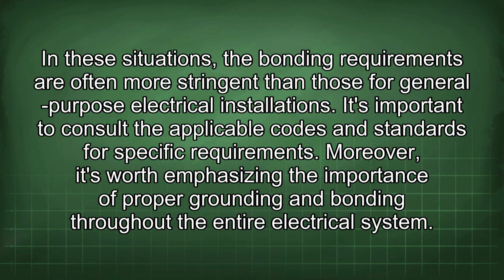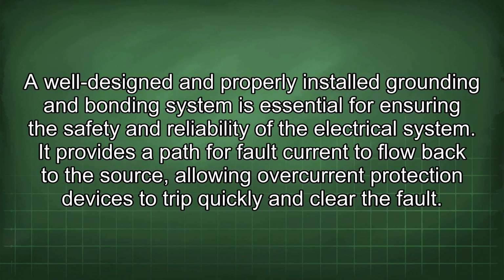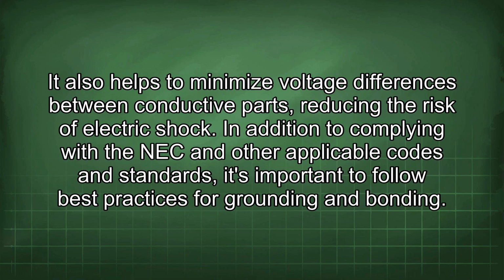Moreover, it's worth emphasizing the importance of proper grounding and bonding throughout the entire electrical system. A well-designed and properly installed grounding and bonding system is essential for ensuring the safety and reliability of the electrical system. It provides a path for fault current to flow back to the source, allowing overcurrent protection devices to trip quickly and clear the fault. It also helps to minimize voltage differences between conductive parts, reducing the risk of electric shock.